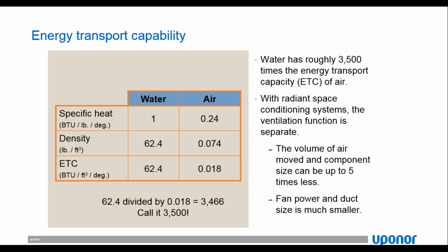That means that a cubic foot of water weighs 62.4 pounds versus 0.074 for air. If you multiply 1 times 62.4, you get 62.4. And if you multiply 0.24 times 0.074, you get 0.018.